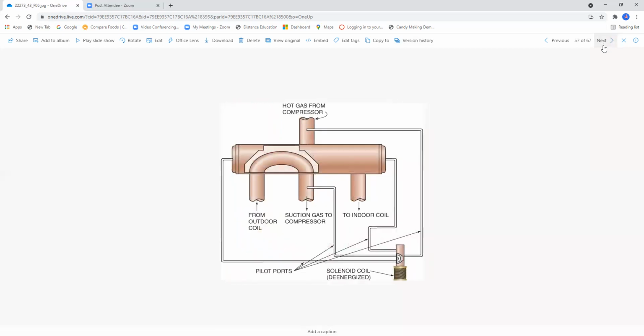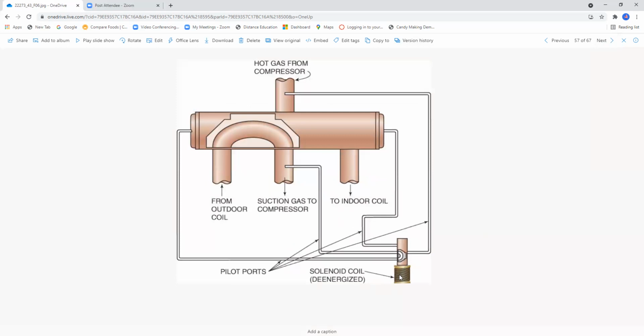Okay, here we have the 4-way valve. This shows the position when the solenoid is de-energized here. So be aware when you see this in the de-energized position, this is probably going to be in the heating mode. Notice that we have pilot ports here. And remember, I had a situation where this pilot line basically developed a leak. I was lucky. I was able to fix this thing out in the field for a customer in Temecula. And to my knowledge, it's working great at this point.